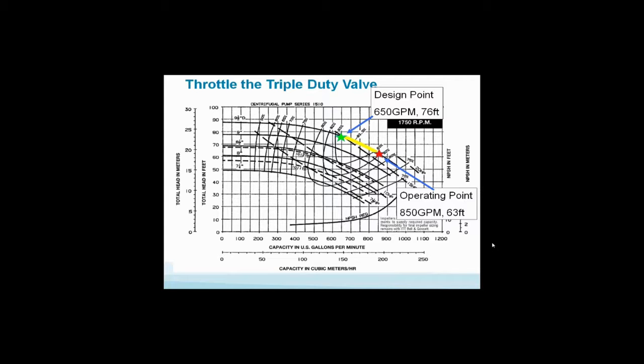That's pretty much the way people like to balance and run off and leave. Does that work? It works. Will the system work? The system will work. What's the problem? We actually saved a little bit of money, didn't we? We went from 17 brake horsepower, at 6 cents a kilowatt hour running continuously, $8,000 to $7,400, and all we did was throttle the triple duty valve. And now I'm at 16 brake horsepower. I'm running at design. What's wrong with that? You're wasting a lot of money and you're not meeting the code. That's what's wrong with it.